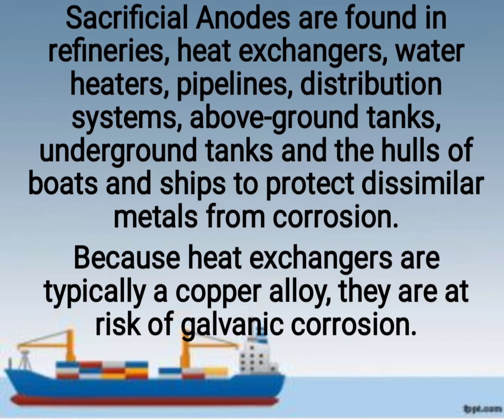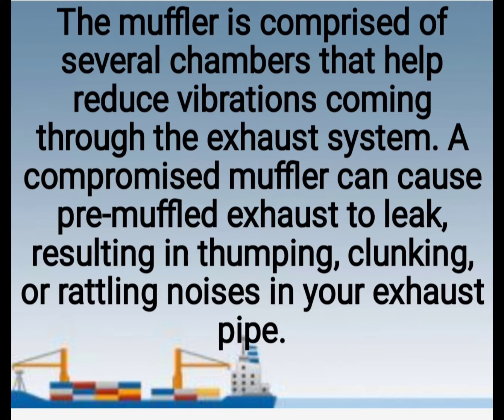Sacrificial anodes in heat exchangers: when to change. Sacrificial anodes are found in refineries, heat exchangers, water heaters, pipelines, distribution systems, aboveground tanks, underground tanks, and the hulls of boats and ships to protect dissimilar metals from corrosion. Because heat exchangers are typically a copper alloy, they are at risk of galvanic corrosion.